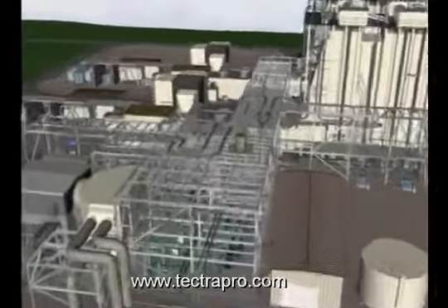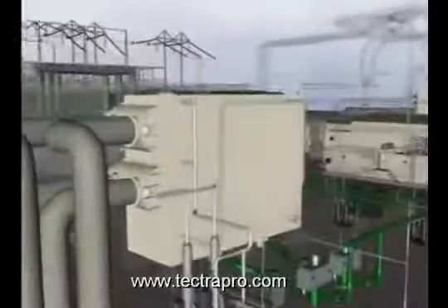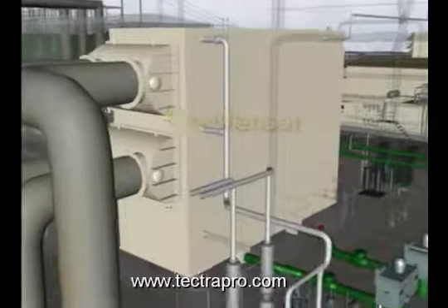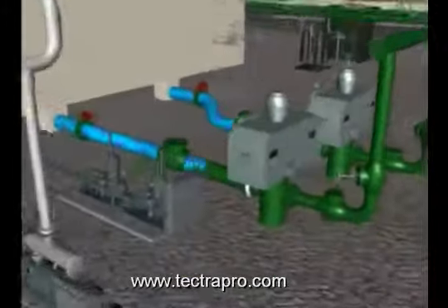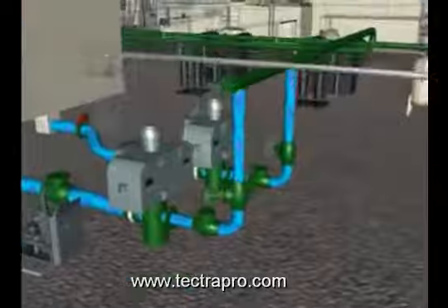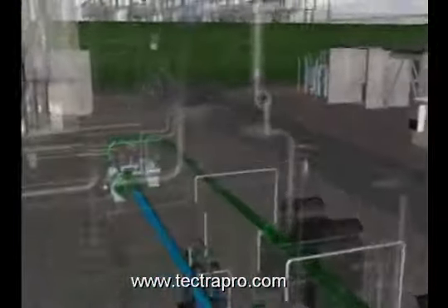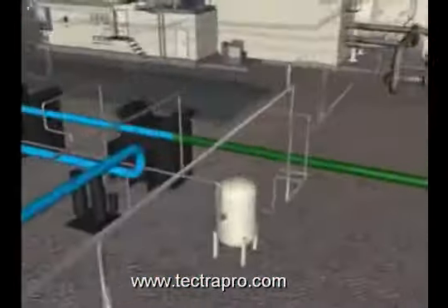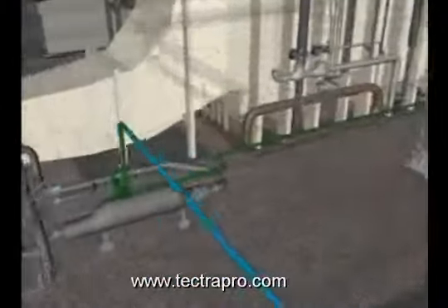The water supply for the HRSG begins with the condensate system at the hot well of the single-pressure deaerating type condenser located at the steam turbine exhaust. Condensate collected in the hot well is supplied by the condensed and deaerated exhaust steam from the steam turbine. The hot well supplies the suction for the condensate pumps.